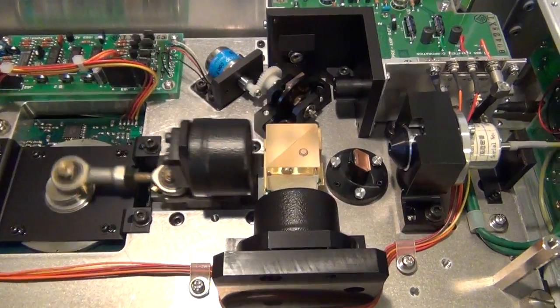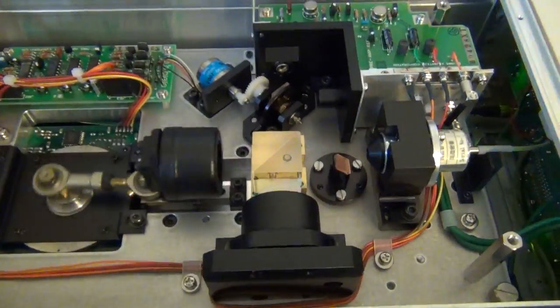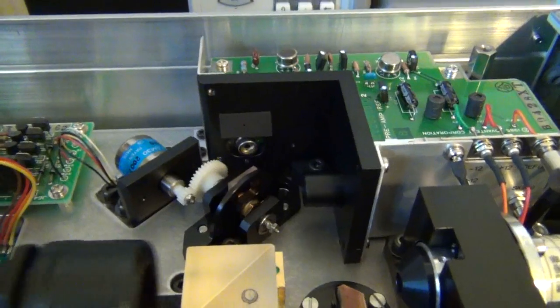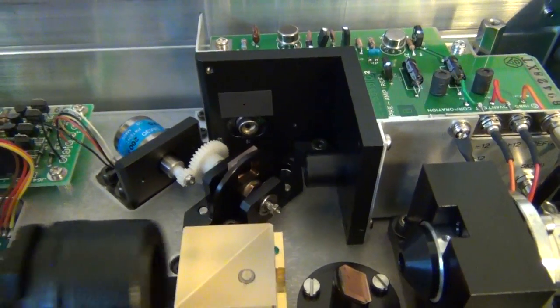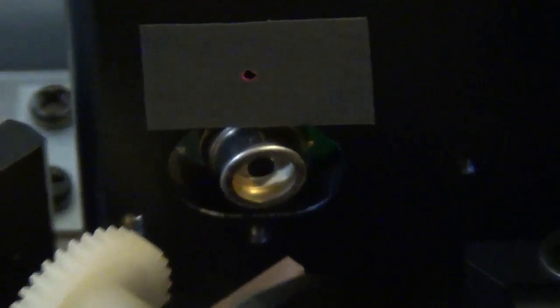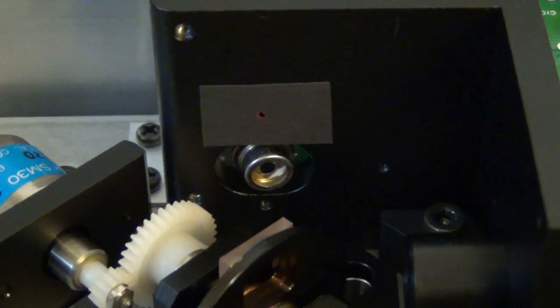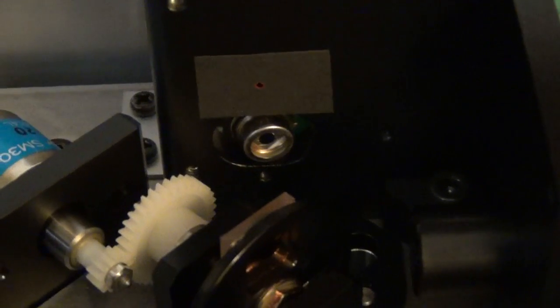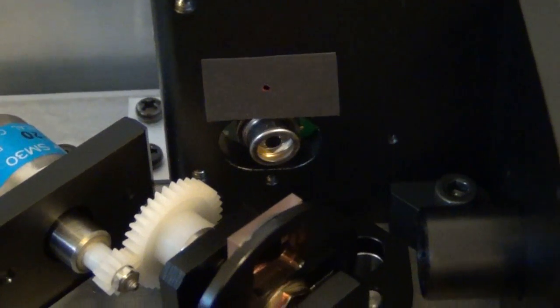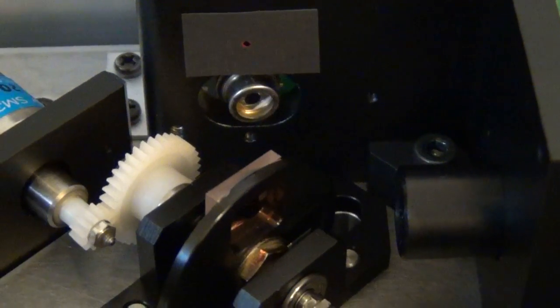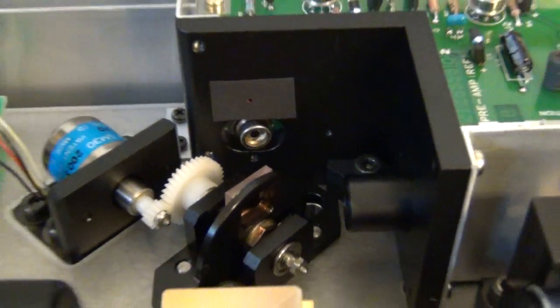But this instrument does something else. If I turn this light off, you can see, if you look closely at where the detectors are, that there is some red light already there. So there is some laser already present there. That's because this thing has a built-in helium neon laser that it uses as a reference. So where does that light come from?